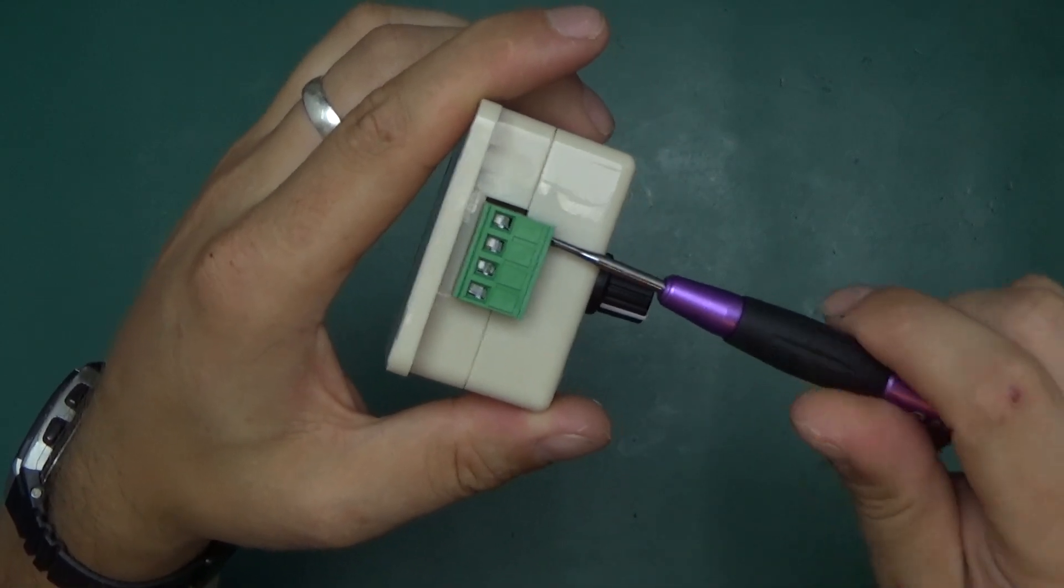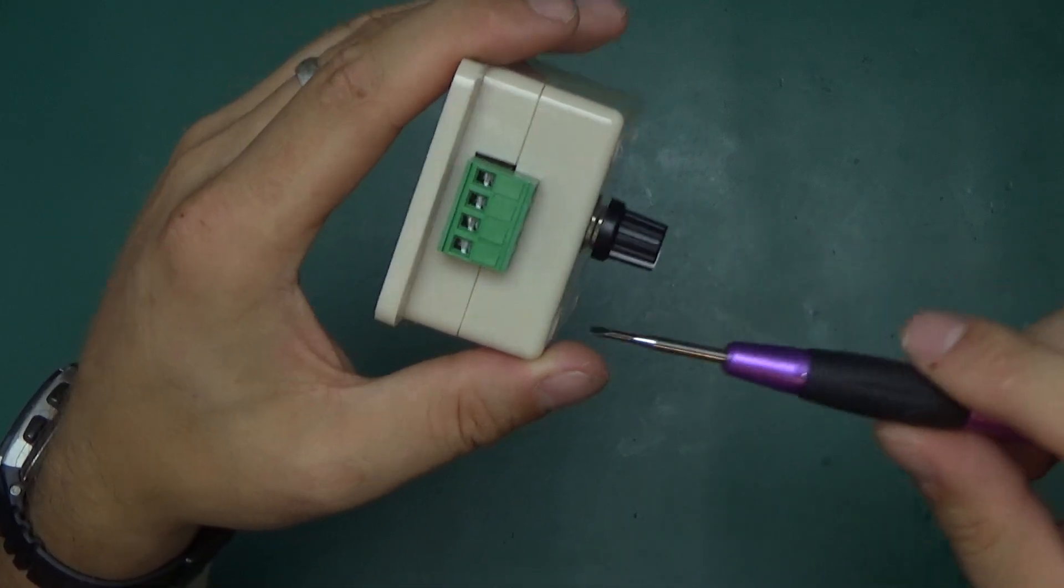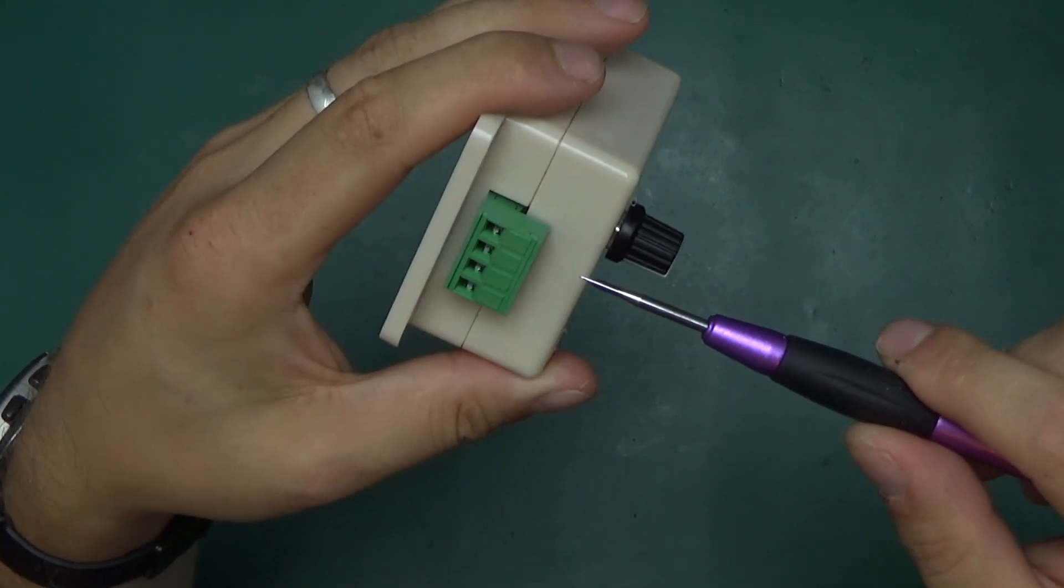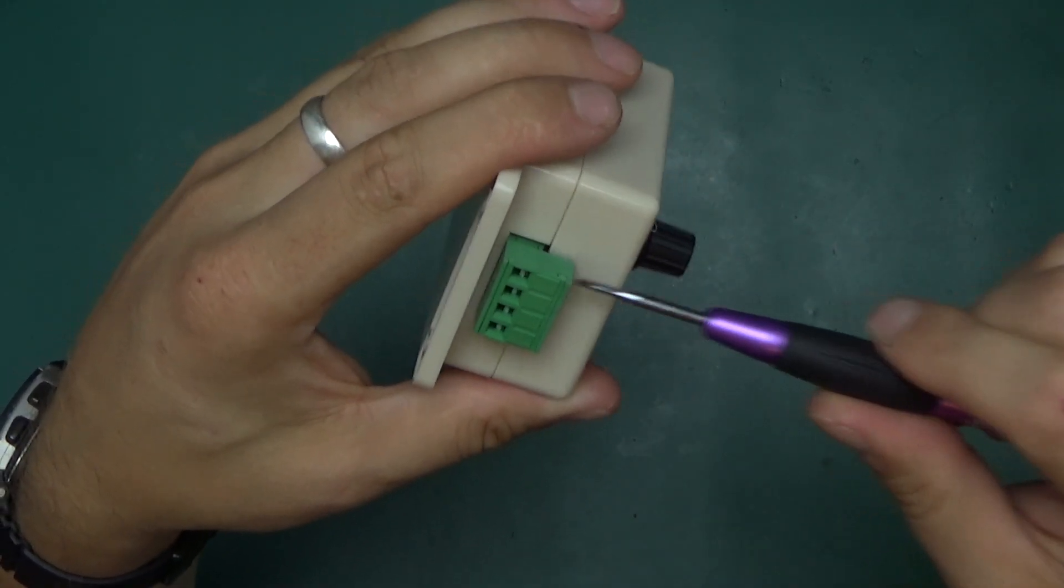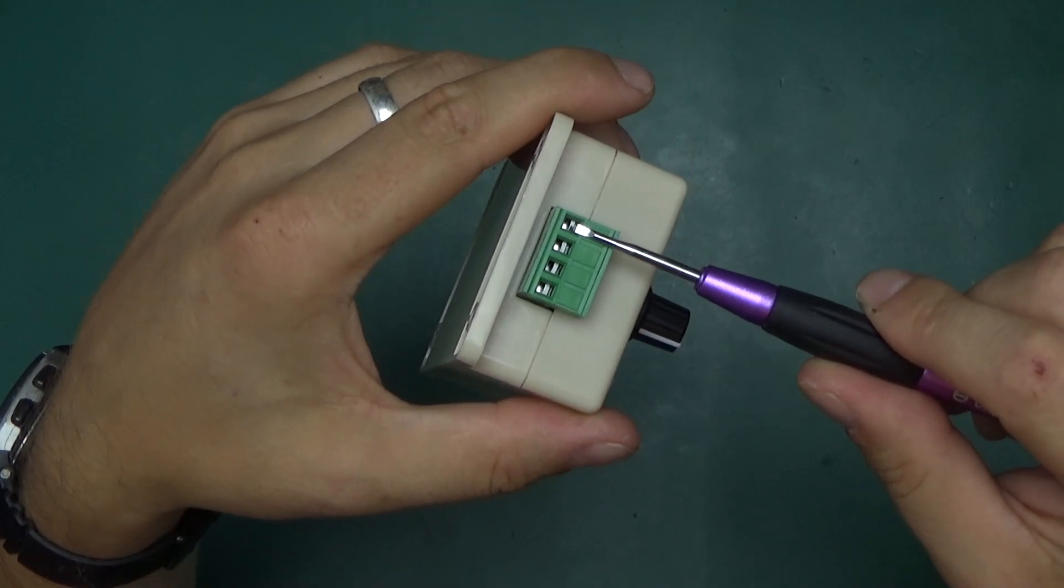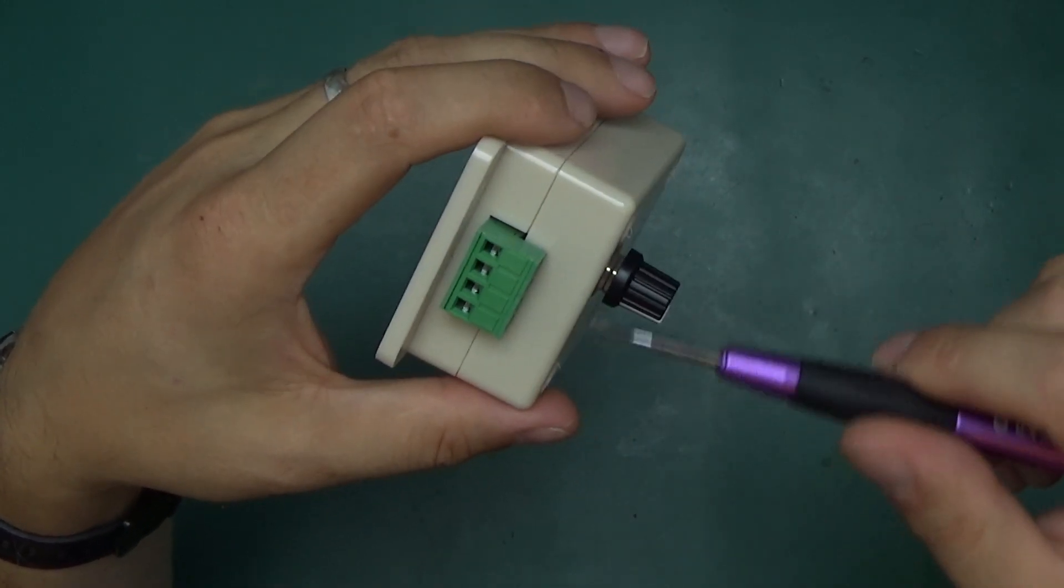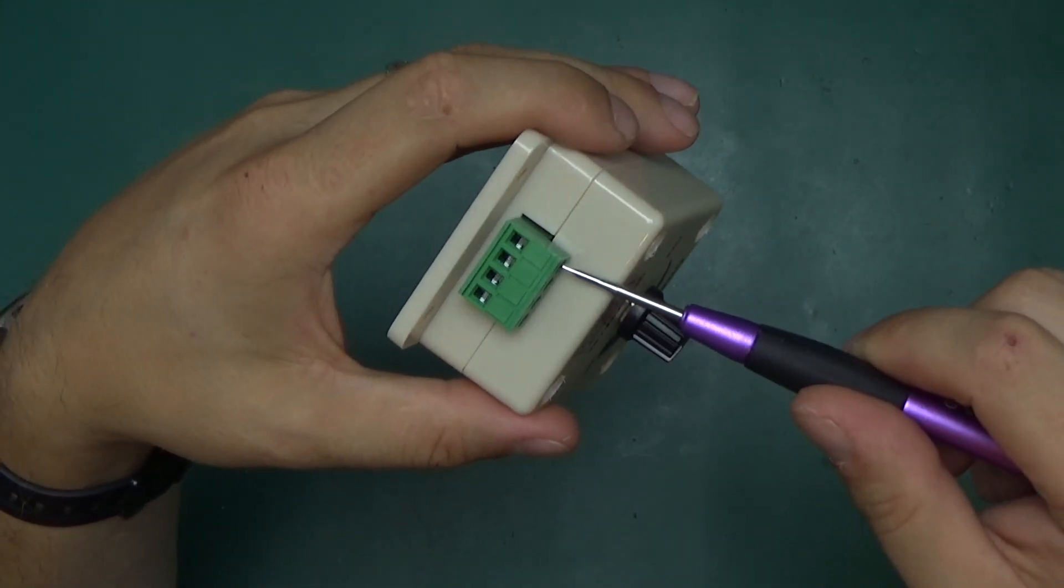Now, there are three types of connectors, screw terminals like this, that I've come across. One is where the screw that you screw in here pushes right against the wire that you want to connect. And those are horrible. Very often they break the wire.